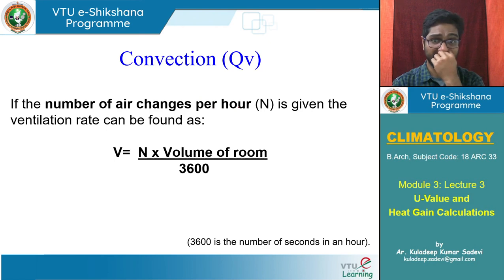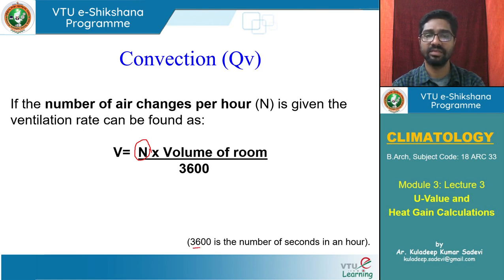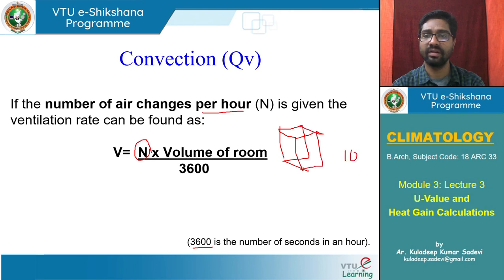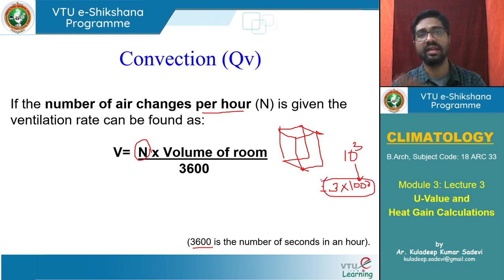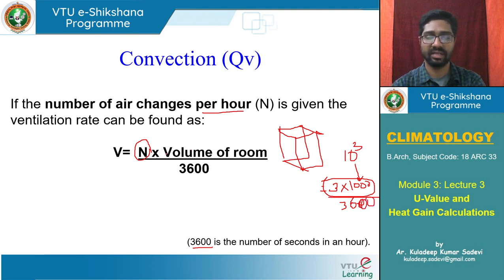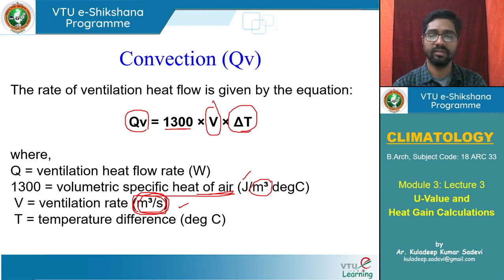The number of air changes per hour is given. Multiplying by volume of the room and dividing by 3600 seconds per hour gives us the ventilation rate in cubic meters per second. For example, a 10 cubic meter room with 3 air changes per hour: 3 × 10 = 30 cubic meters per hour, divided by 3600 gives the ventilation rate per second. This ventilation rate is used in the formula to calculate heat gain through convection.